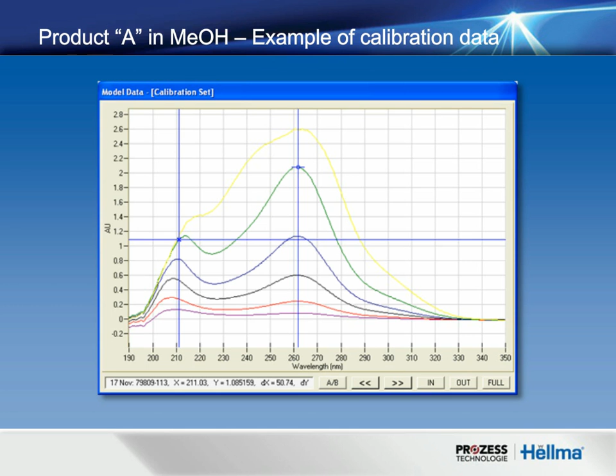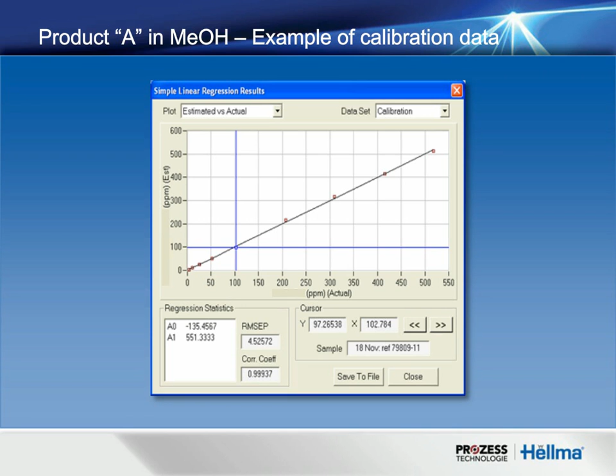Before I skip forward, I should also mention the range that typically we'll monitor starting around 190 nanometers. And we have various options for the longer wavelength and depending on the necessary resolution. So from 190 to 400, 190 to 600, or 190 out to about 1 micron, depending on the needs and what the system is going to be used in. So from those absorption spectra, we can create this quantification model that now relates the absorption units to a concentration level, and you can see here that it's a fairly linear response over a fairly broad range between just more than around single-digit ppm up to 500 ppm.